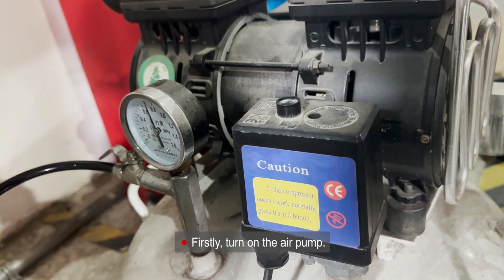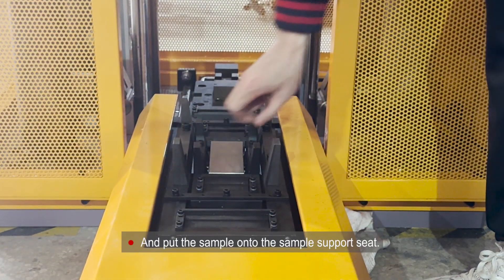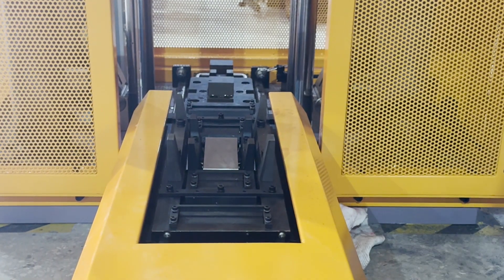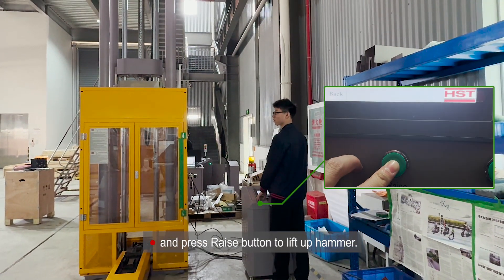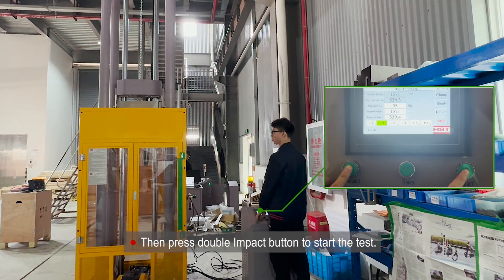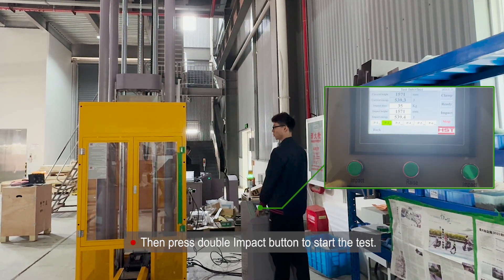Firstly, turn on the air pump and put the sample onto the sample support seat. Click the Test button, choose the corresponding sample size, and press the Raise button to lift up the hammer. Then press the Double Impact button to start the test.